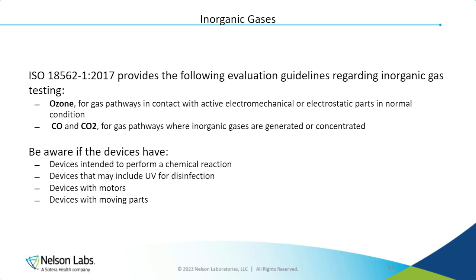Then there's some devices with lower risk, but they are still possible to be questioned. These are devices with motors in the gas pathway. If the gas a patient breathes goes through an electric motor or an electric discharge from the motor, it could produce ozone. And then lower risk, but still within the realm, is any device just with moving parts in general.